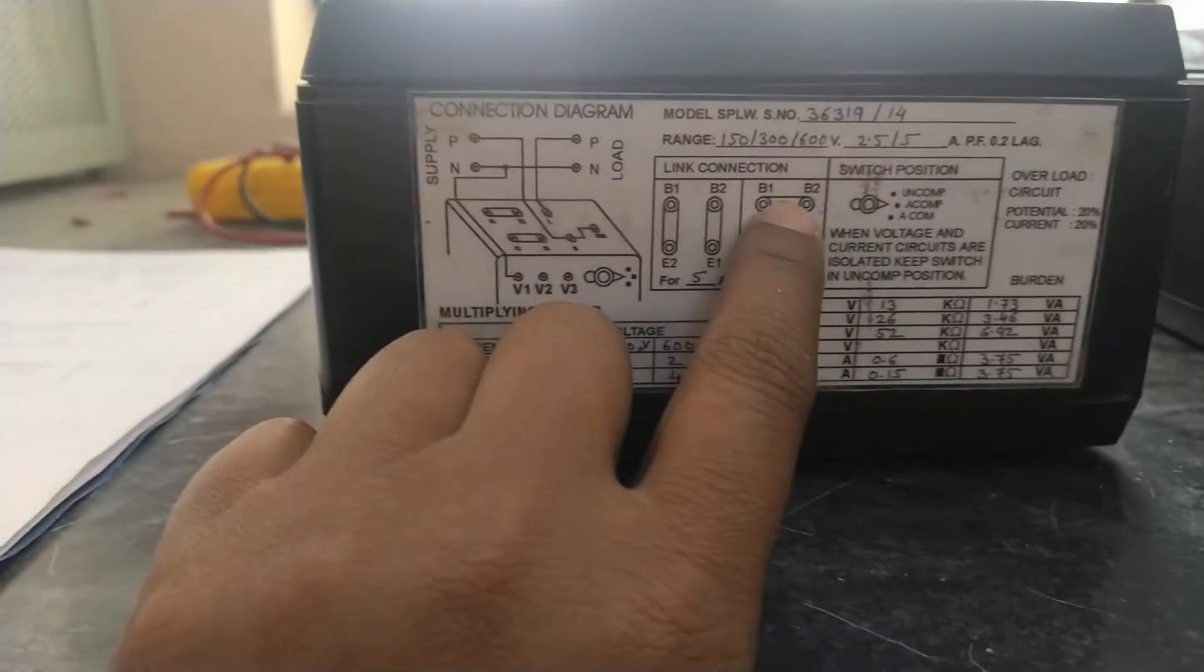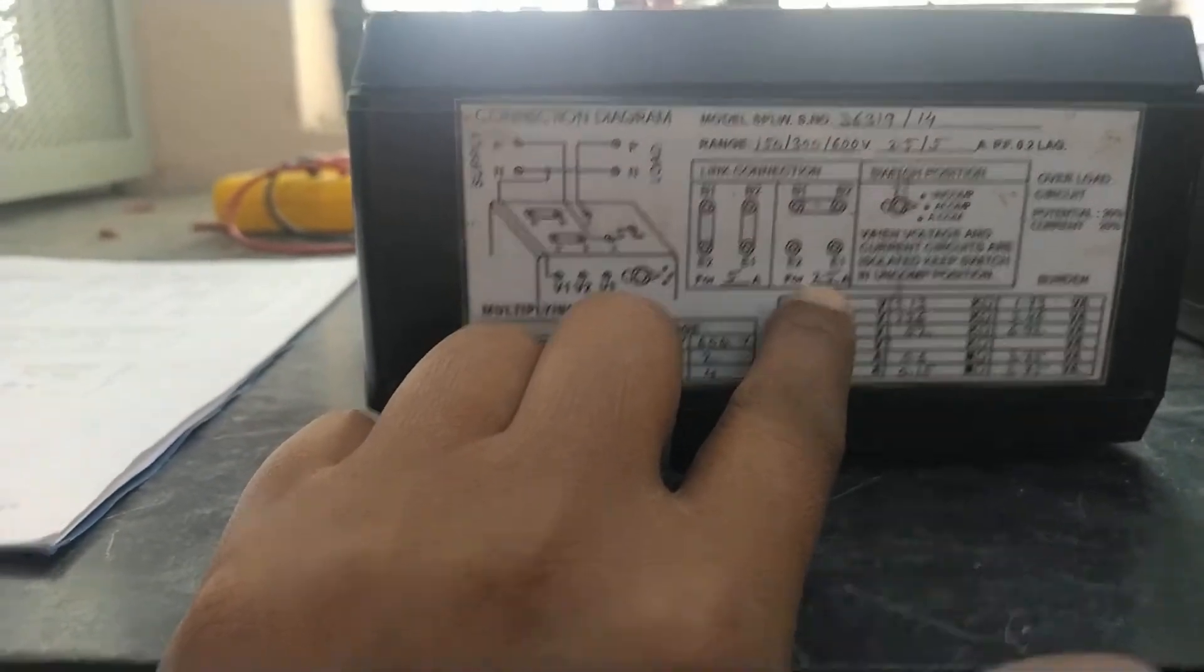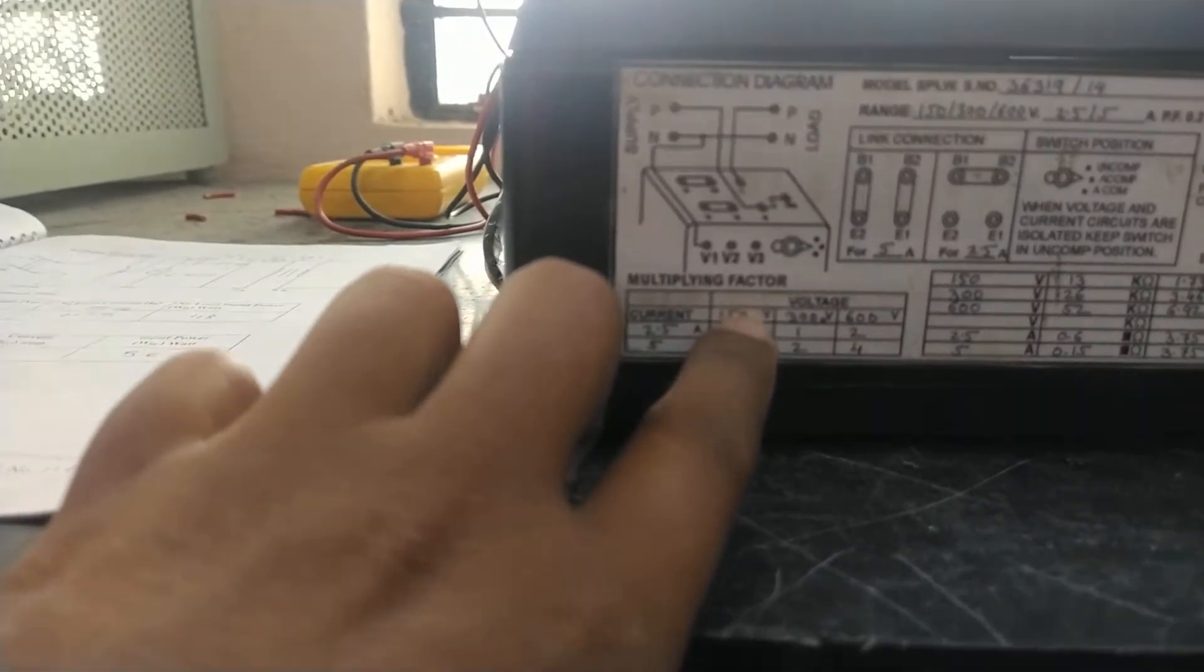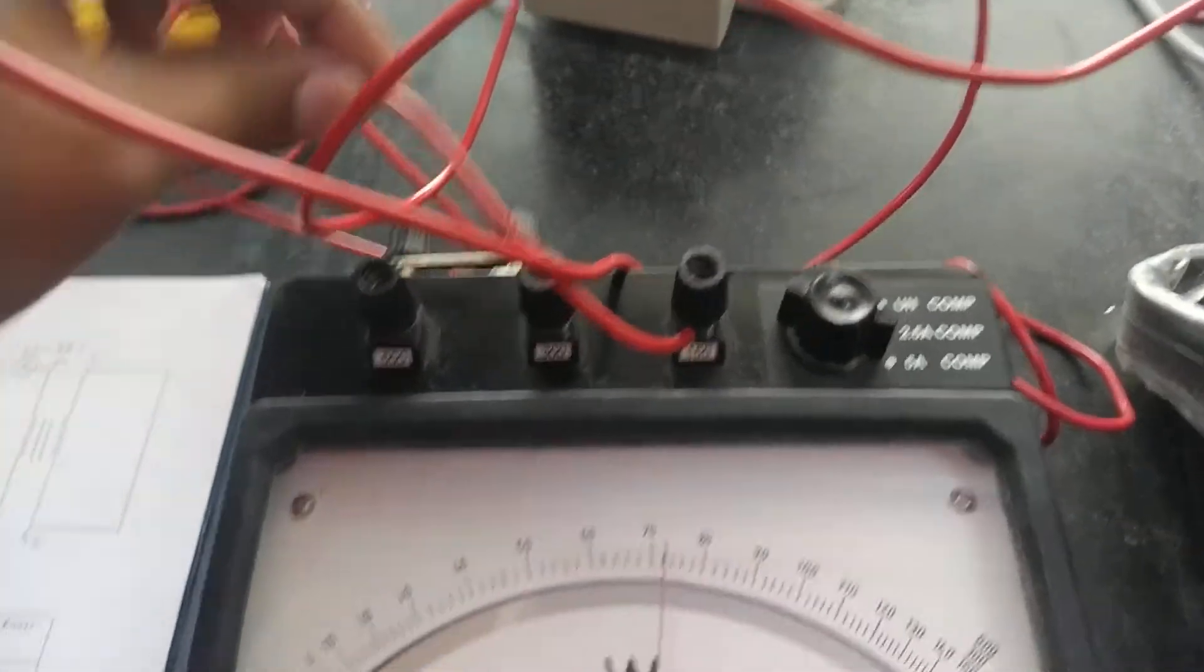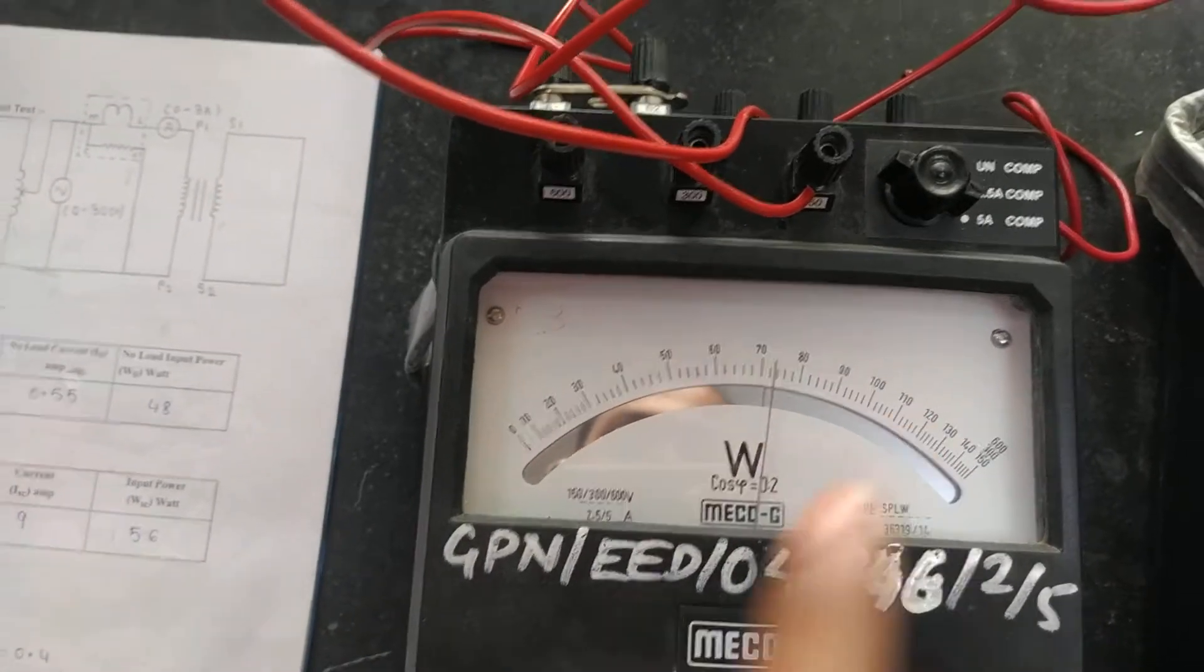So if we short B1 and B2, then current will be 2.5 ampere. So if current is 2.5 ampere, and we have connected it to 150 volt, so multiplying factor will be 0.5. So here we have connected it to 150 volt, so whatever reading we are getting on wattmeter, we have to half it.